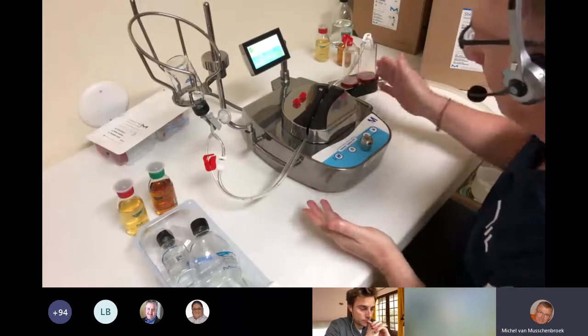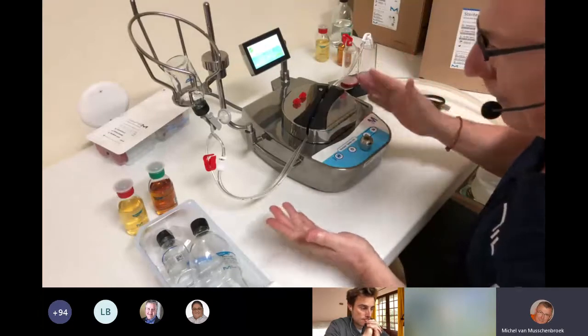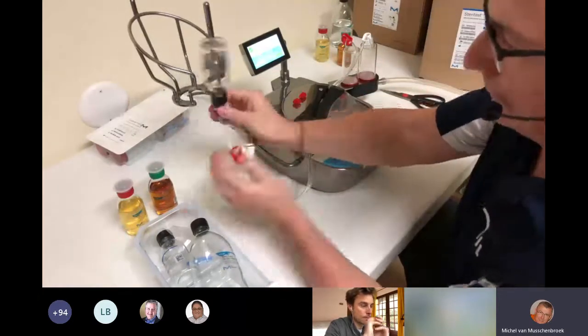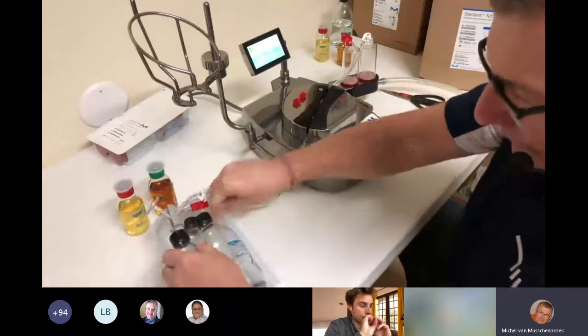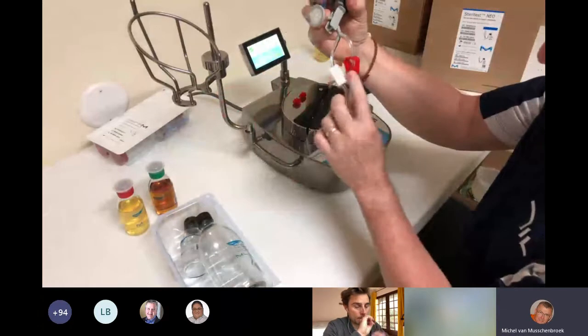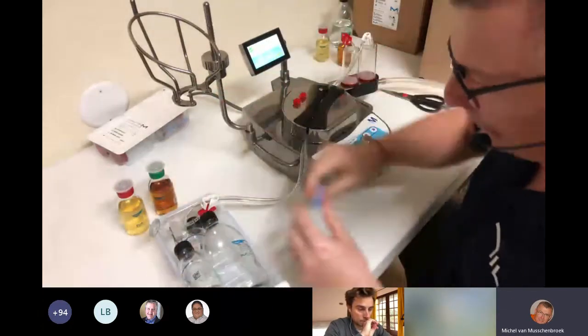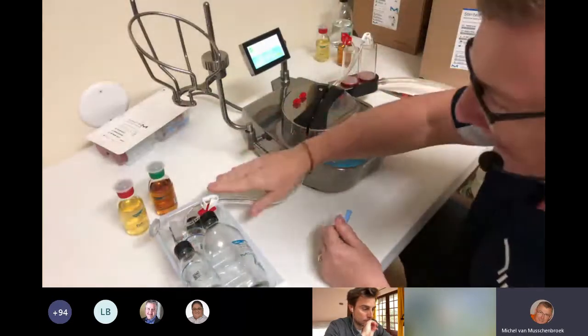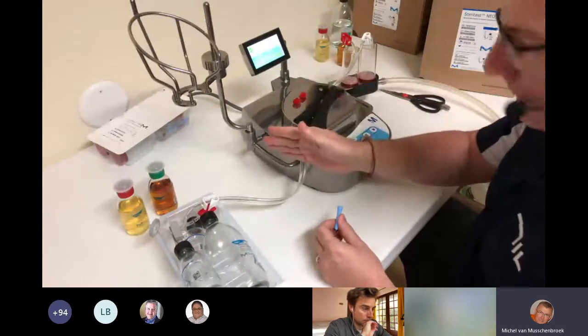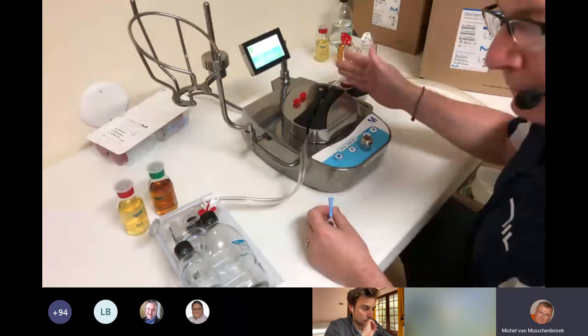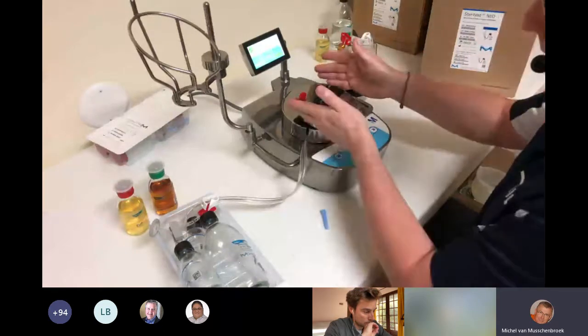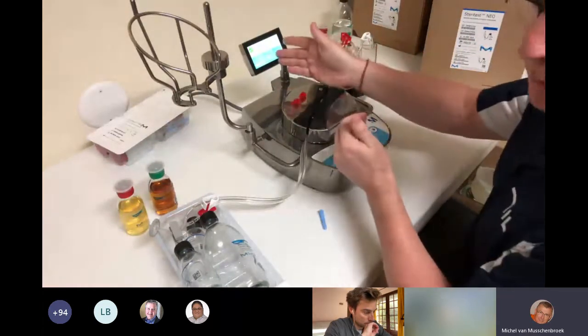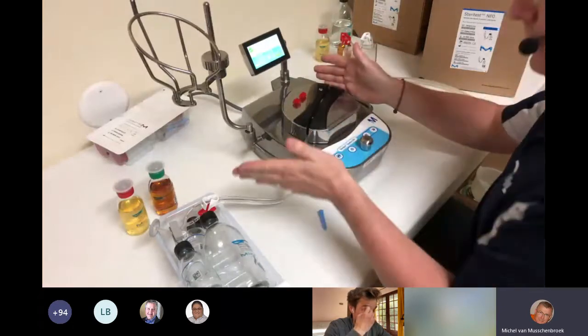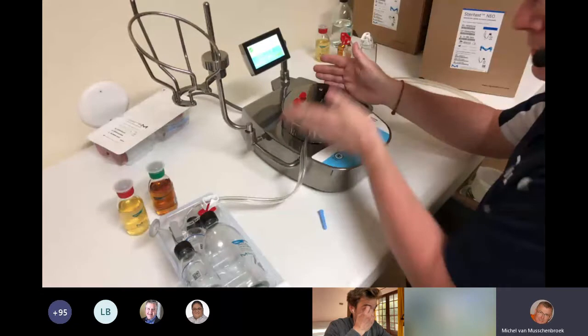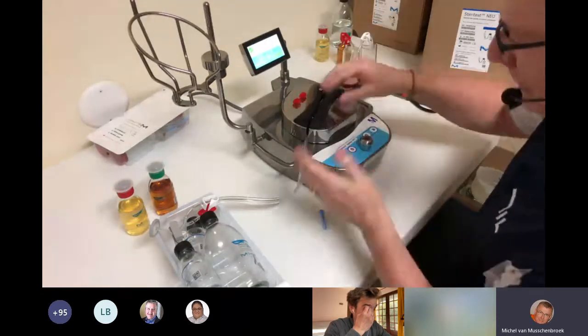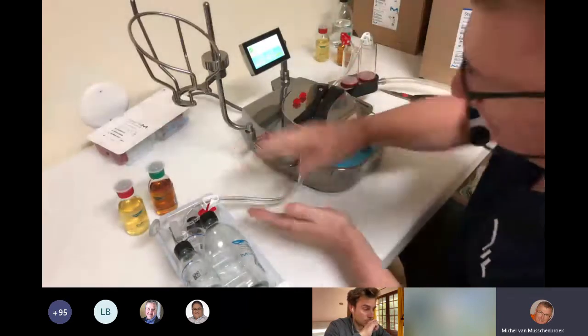We also want to separate the two. We have TSB and FTM. In order to do that, we have clamps on each of the tubings, red and white, and this helps bring it through. We want to clamp ahead of the pump head, not behind it. If we clamp behind it, you run the risk of elevating the pressure inside the tubing and getting a false pressure alarm. Because what's happening at that point is the pump is trying to push. It's a peristaltic pump. It's trying to push through, and what happens is the sensor will go off. So we want to clamp upstream of the pump.